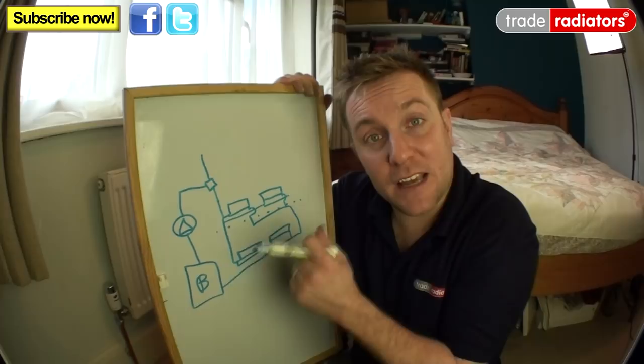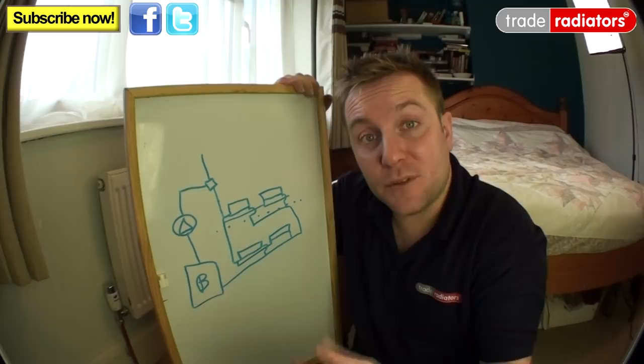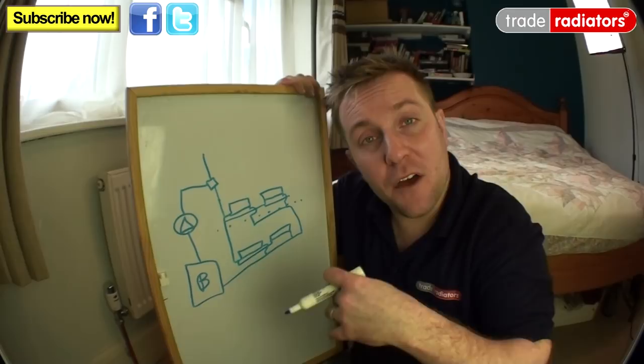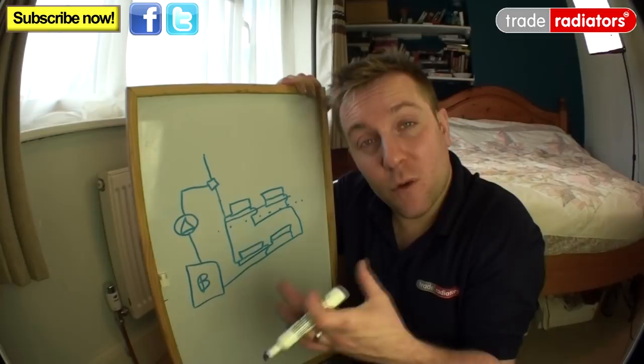The other reason we balance a heating system is sometimes you'll find that all the radiators upstairs and downstairs are getting hot, but there's one radiator on the extremity of the system that isn't getting warm. So you'd balance all those radiators out by shutting all the radiators that are getting hot, opening them up half a turn, and then giving it half an hour — and you should find that all the rads, including the one that didn't get hot before, will also get warm.